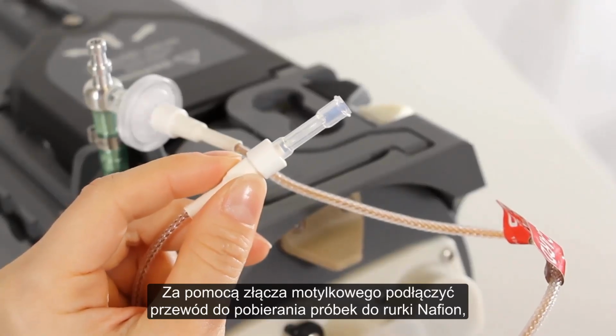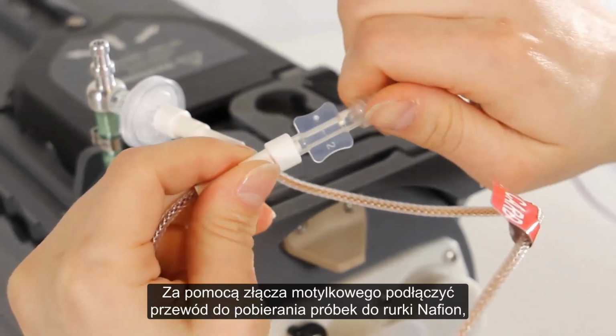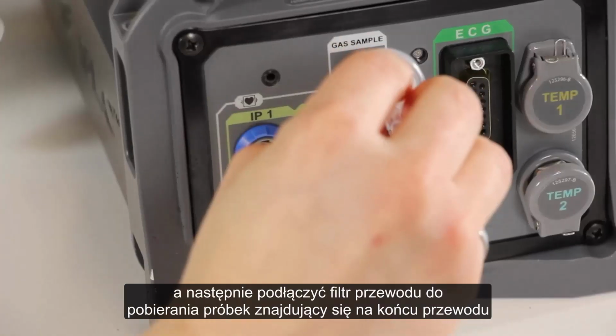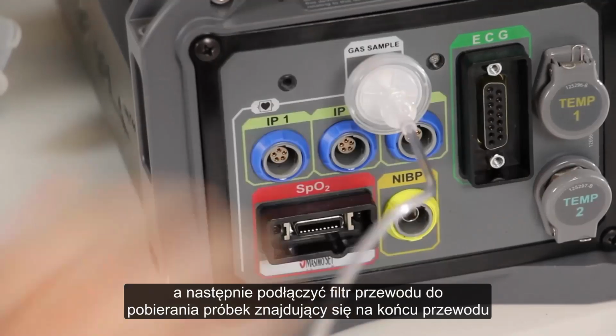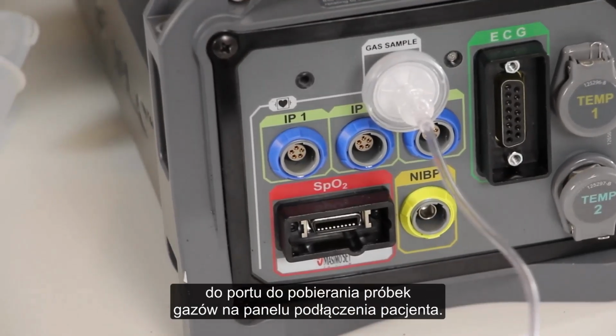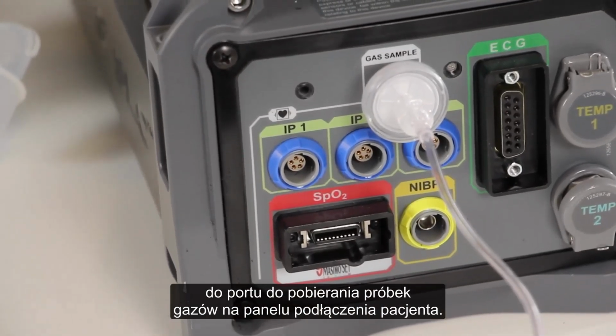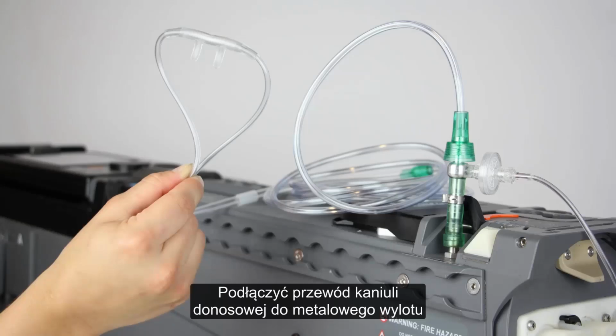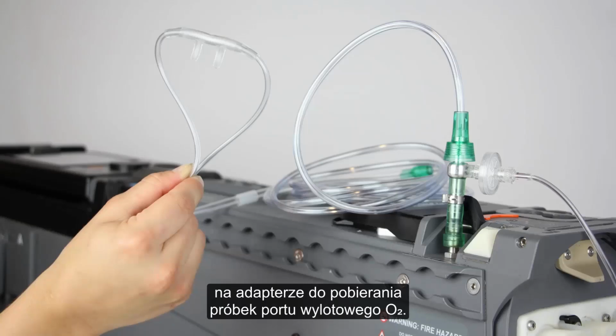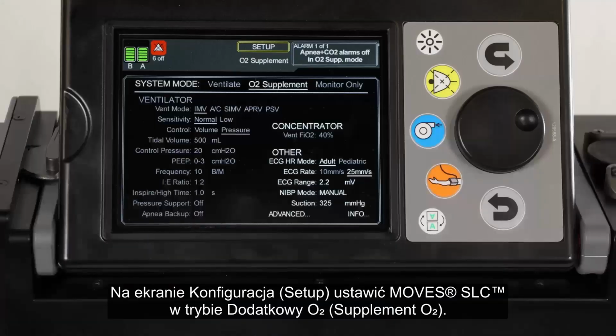Use a butterfly luer connector to connect the sampling line to the Nafion tube. Then connect the sample line filter at the end of the sample line to the gas sample port on the patient connection panel. Attach the nasal cannula line to the metallic outlet on the O2 outlet sampling adapter. On the setup screen, configure Moves SLC to operate in O2 supplement mode.